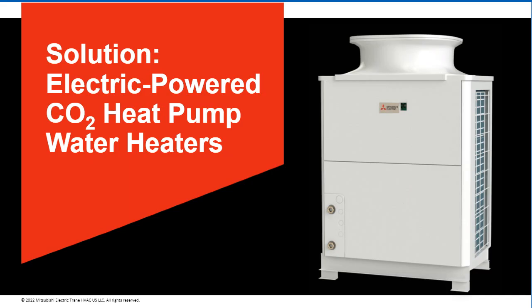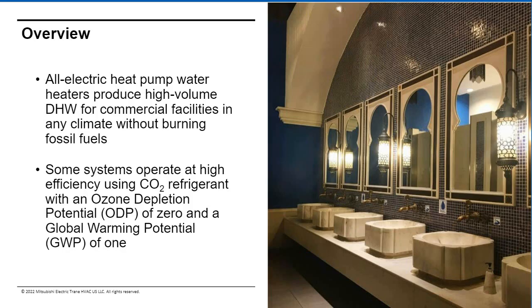So what is it? What does it look like? On the right here, you can see a picture of our CO2 hot water heat pump. We'll go into some of the details, but over the years in the global marketplace we have looked at different ways to accomplish this, and we have various products that have been launched globally. Now we're looking to launch this CO2-based version, which is really the best solution for serving domestic hot water and bringing that low water temp up to storage water temps at a very good COP and efficiency.